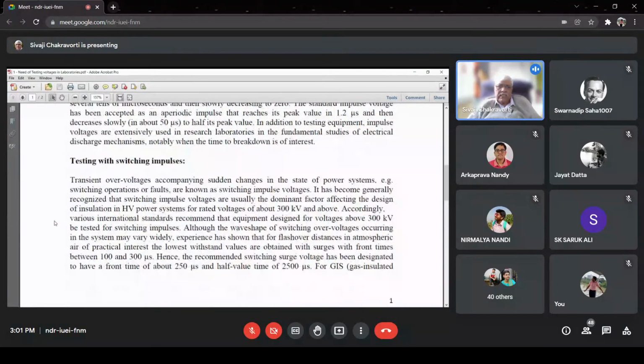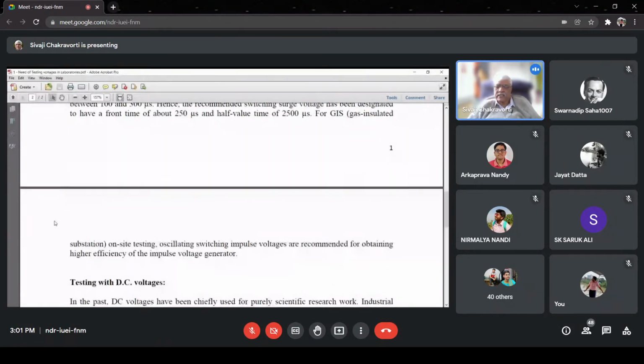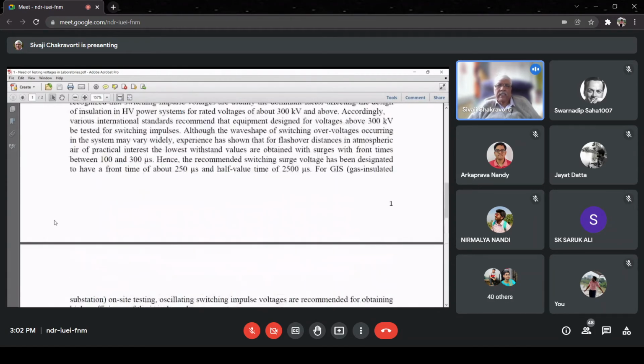Now, one more thing has come into our power system. This is called GIS, or gas insulated substation. And it has been found that in this gas insulated system, these switching impulses are very, very important because they can create a lot of problems if not properly taken care of. So, considering all that, we need to generate the switching impulse voltages in our laboratory. So, these are the four different types of voltages.